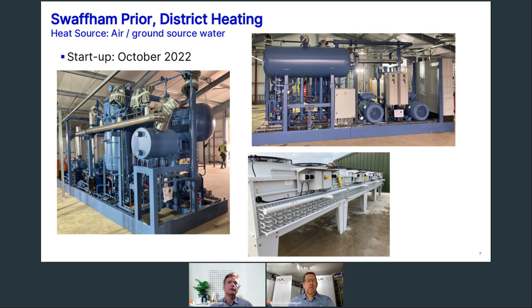Of course, you need a bigger ammonia charge, because you have the ammonia directly in the coil in this case. But again, in general it's the standard design on the heating side with the low charge plate and shell heat exchangers. So that is all I had for this session.